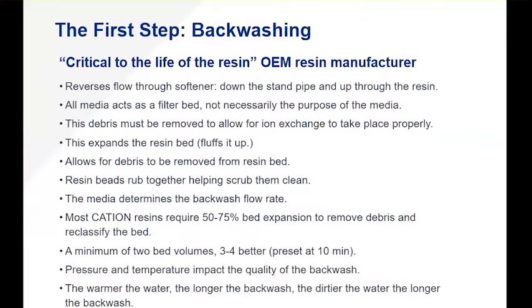If we don't backwash properly, what happens is we start to coat the resin further and further down the tank with debris, and eventually it will start to push through and come out to service. Then you're left in a situation where you have to do an immense amount of cleanup or exchange the resin — and there's probably nothing wrong with the resin at that point, it's just so filthy you can't use it anymore. I've had to increase the backwash of my own system at home simply because my water treatment plant changed its process and I have more particulate in my water.